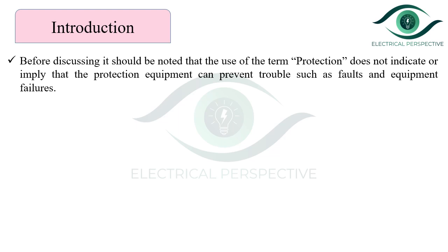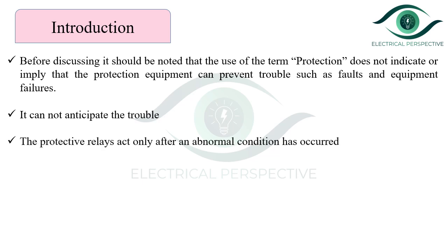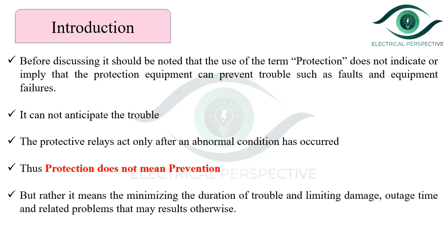Before discussing the actual topic, it should be noted that the use of the term 'protection' does not indicate that protection equipment can prevent trouble such as faults and equipment failures. It cannot anticipate trouble. The protective relays act only after an abnormal condition has occurred. Thus, protection does not mean prevention, but rather minimizing the duration of trouble and limiting damage, outage time, and related problems that may result otherwise.